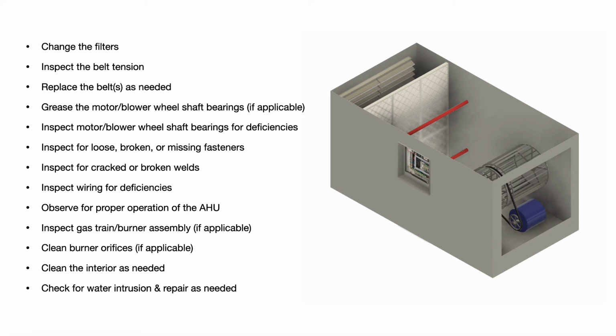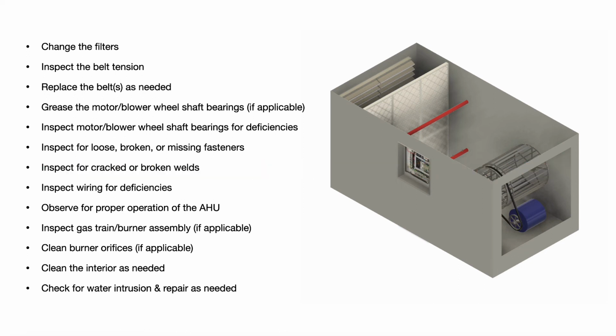Inspect the entire unit for loose, broken, or missing fasteners, broken welds, cracked welds. Inspect the wiring for breaks, abrasions, burn marks, and observe the AHU for proper operation. Is it actually working properly? Does it turn on when it's supposed to, turn off when it's supposed to? If you have a gas train for heating, is that working properly? Inspect for cracks on your gas train, especially on your burners. And the burner orifices a lot of times need to be cleaned out.